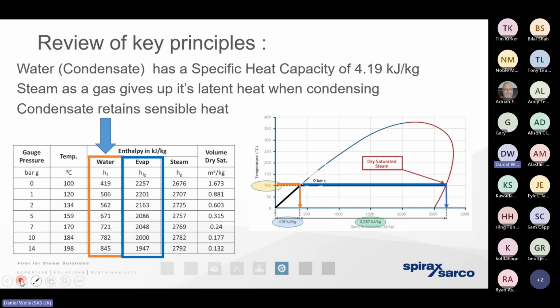So keeping the steam dry is fundamentally important for efficiency purposes. But the steam tables also tell us that there's some value retained within that condensate, for the simple reason that when steam gives up its heat energy and condenses, it gives up its energy, but it doesn't cool down. So as far as the heat exchange is concerned, as far as the infrastructure is concerned, that condensate is unwanted. It's a byproduct. We need to get it away so that we don't contribute to that inefficiency, but also so we don't get mechanical damage through an excess of erosion, corrosion, and water hammer.